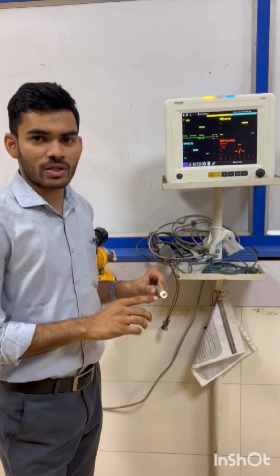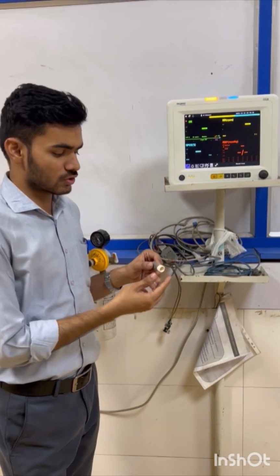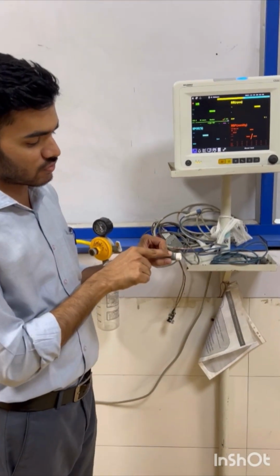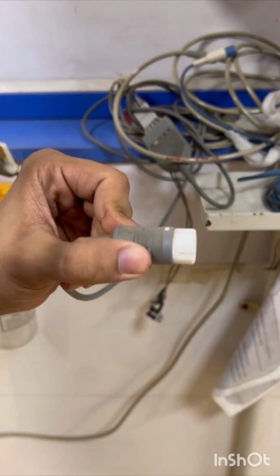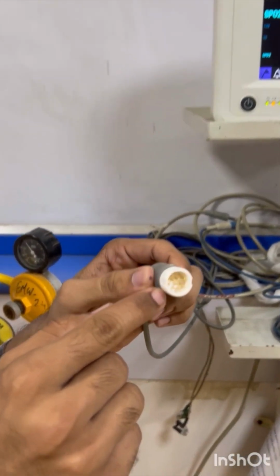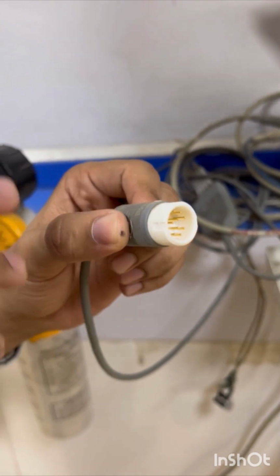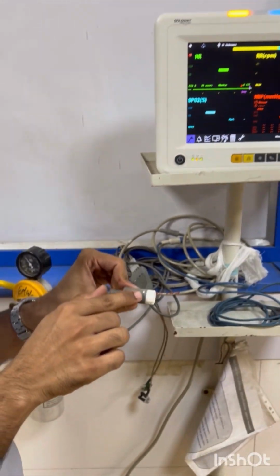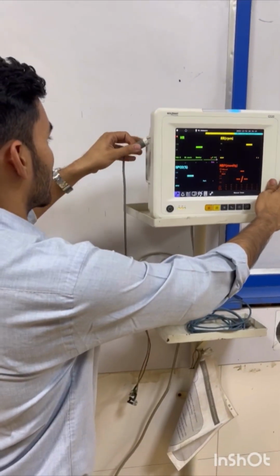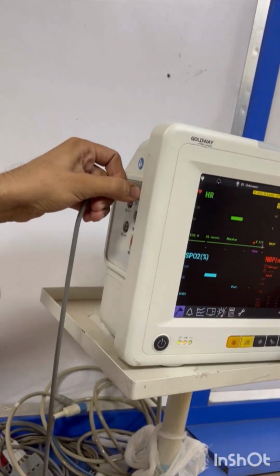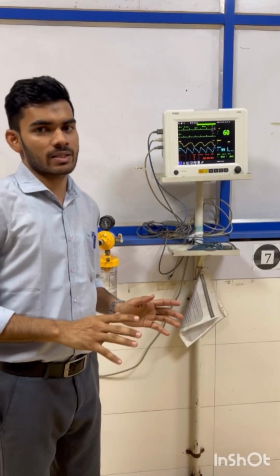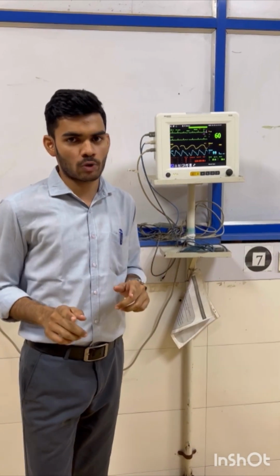Now I will show you how to connect accessories to the patient monitor. So this is the ECG cable. Make sure this white dot is always facing upward side. Otherwise the connectors you can see inside here will get bent. Then you can't use the probe. So make sure this white dot is on upward side, and you just have to press it to the ECG socket. You are using ECG cable. Make sure the lead placement is proper.